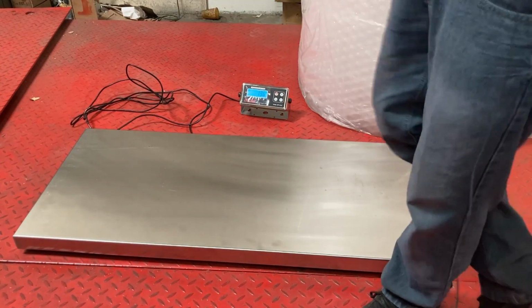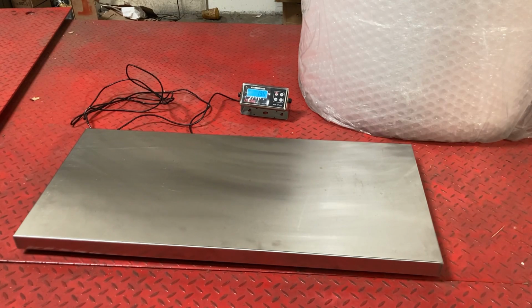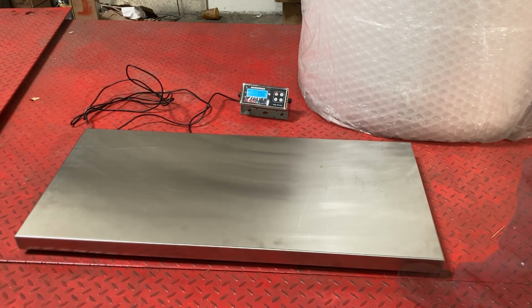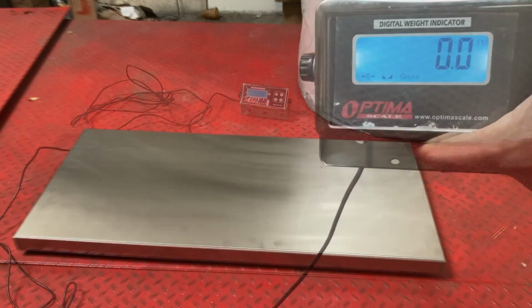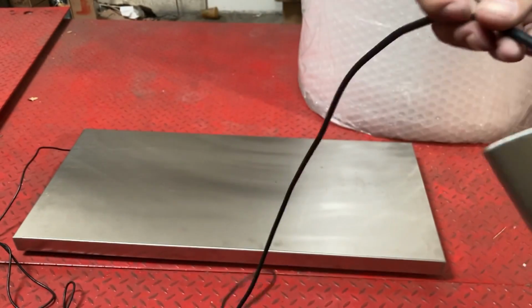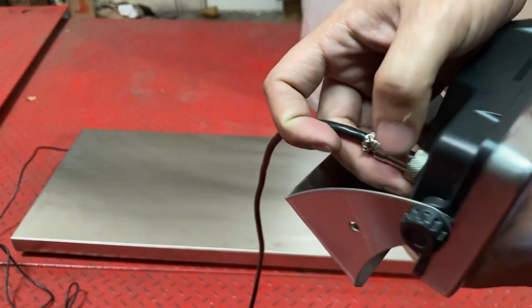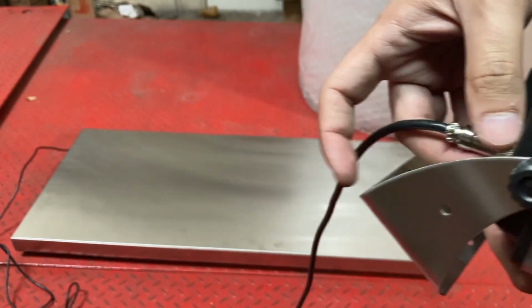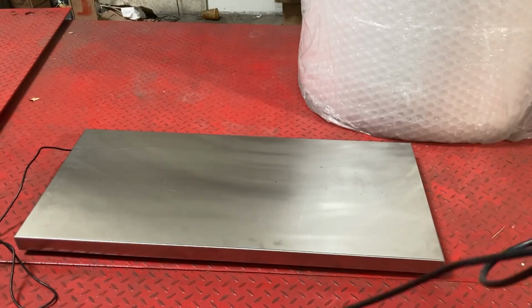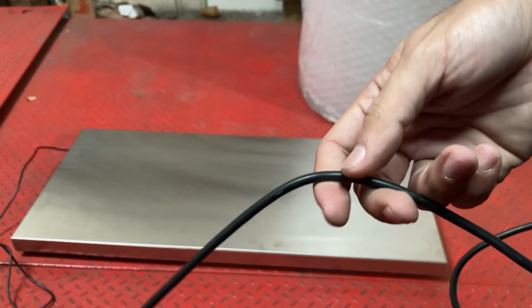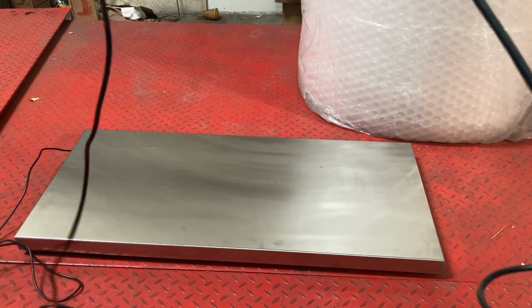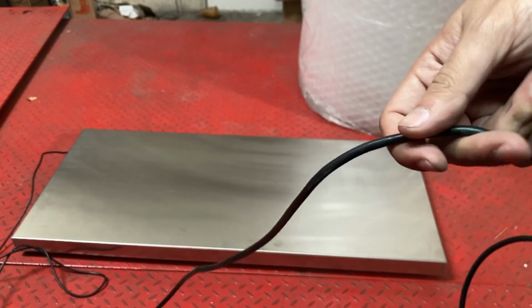So always verify that your feet are not screwed in all the way, because a lot of times they'll still give you the error 6 even though you're not doing anything. I have a vet scale here, so what we're going to do is now try to get to the calibration and see if we get that to work. So this is important before a calibration, is actually inspecting the cable itself. So make sure this connection is tight in there and run your hands along the cable, and if you see any cuts or smashes in the cable, that could be causing your issue with not sending the signal properly.